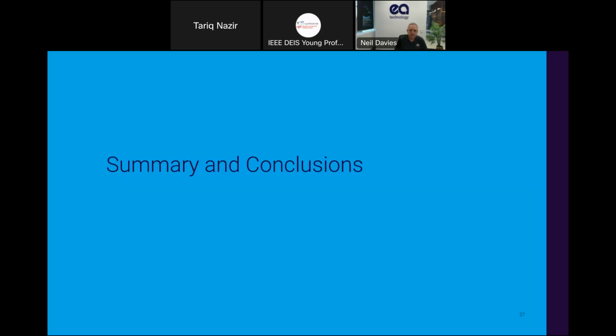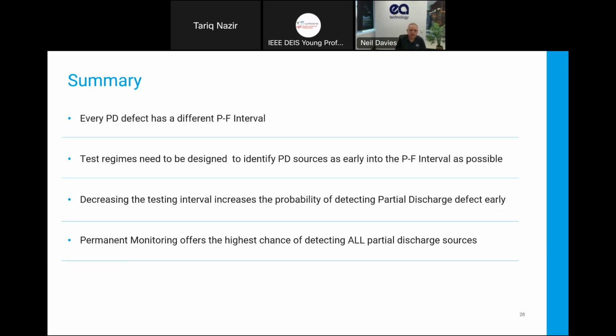Okay. So coming up towards the end to allow time for questions. So the summary and conclusions on that is that every PD defect has a different P-F interval. So what you need to be thinking about is designing the test regimes. Yes, they need to be there to identify the sources as early as possible. And if you decrease the testing interval or put permanent monitoring on there, you will detect more of these short P-F intervals. However, that may not be the most cost-effective solution for whole large networks.